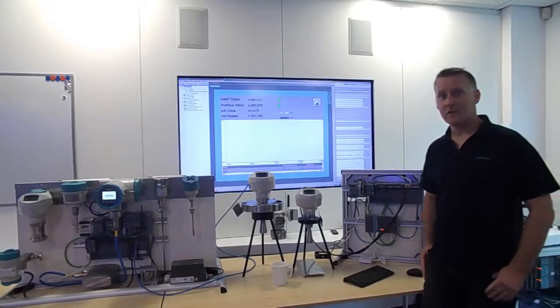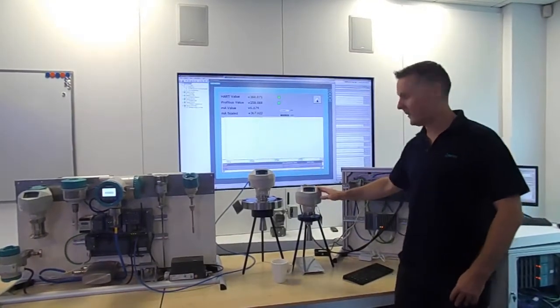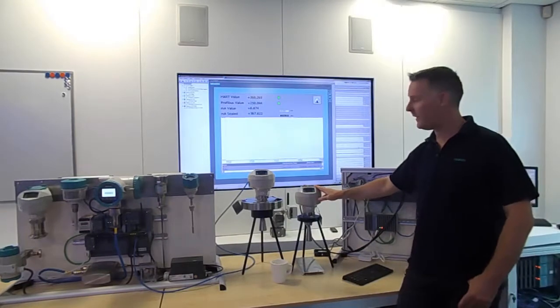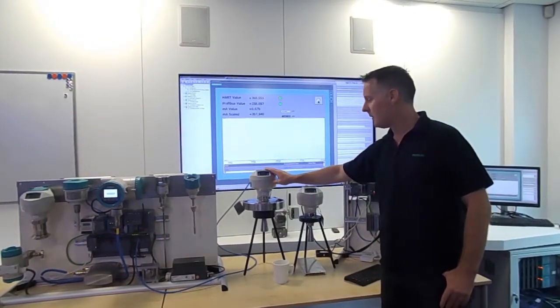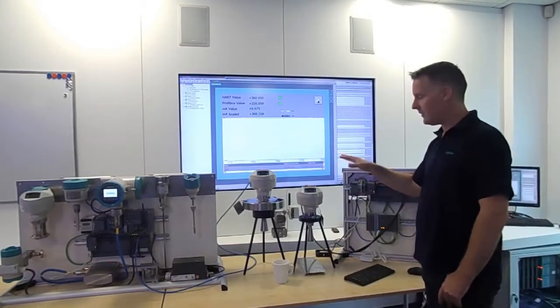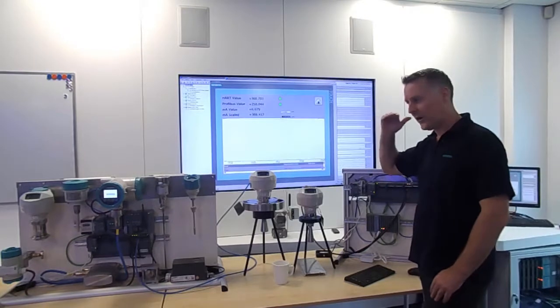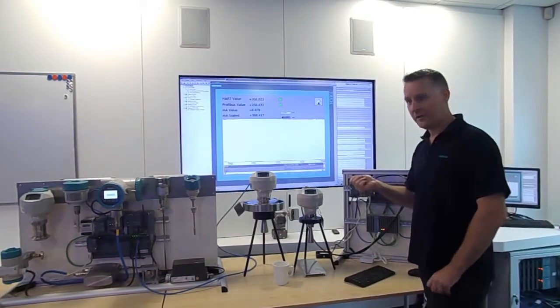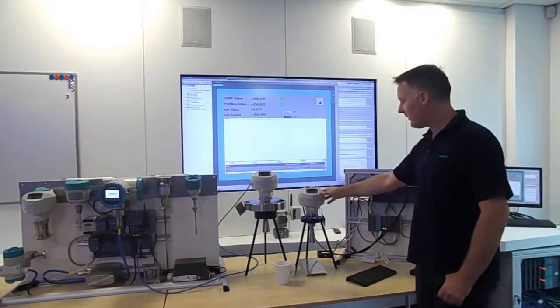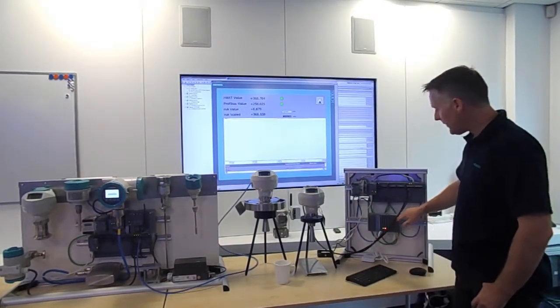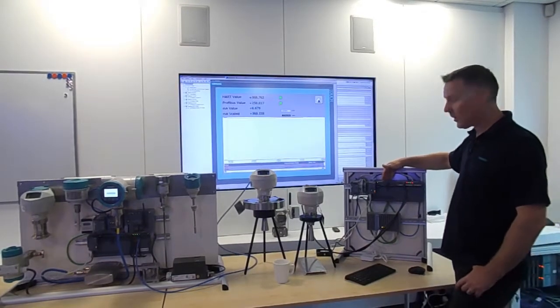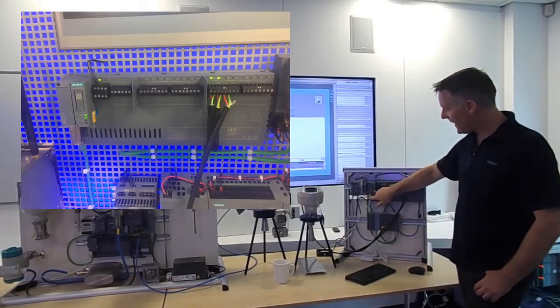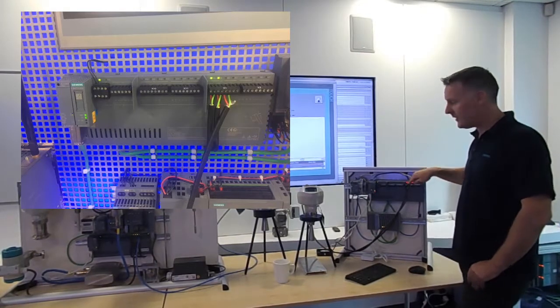Okay, so we're going to take a look at the hardware that we're using to test these two radars. So here we have the Profibus radar and the one on the taller stand is the 4 to 20 radar. So this is why we have slightly different distance readings, but we're focusing on how stable these are rather than accuracy at this point. So the Profibus radar is connected by one section of cable about a meter long to our new Siemens compact field unit which is ProfiNet to Profibus PA, plug and produce capability.